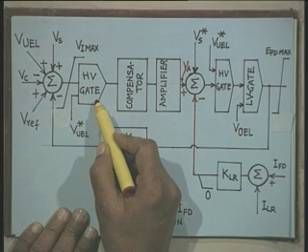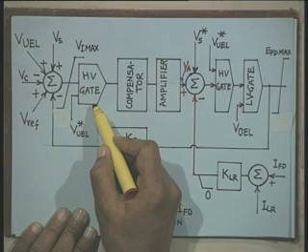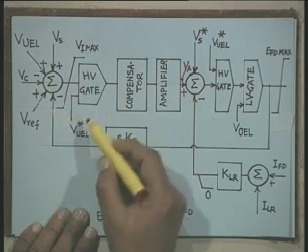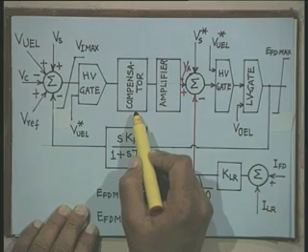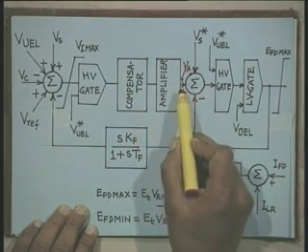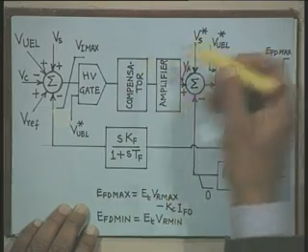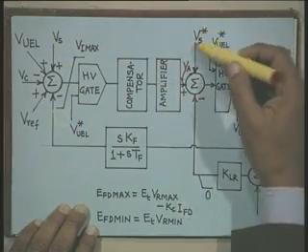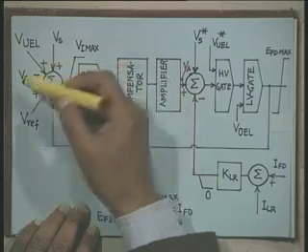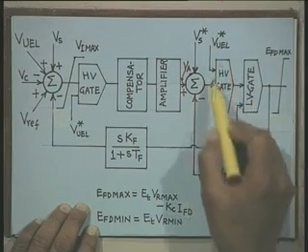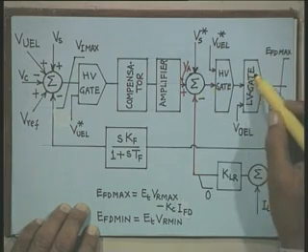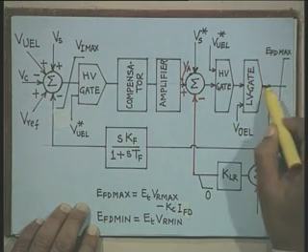It is fed to the HV gate to realize the under excitation limit, then there is a compensator which is put here again. Then the amplifier, and the output signal which comes here is VS. Another point shown here is that the stabilizing signal can be put at this point or at the summing point itself. There are two alternative ways you can put the stabilizing signal. This is fed to the under excitation limiter, then we have the over excitation limiter, and we get the output voltage from this.